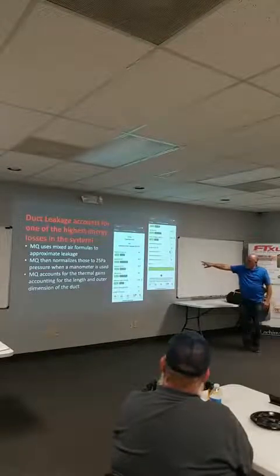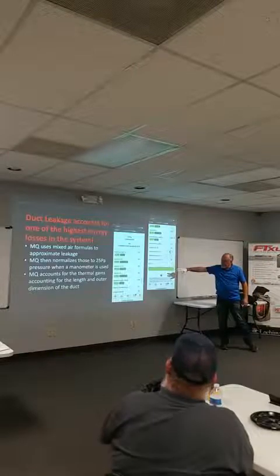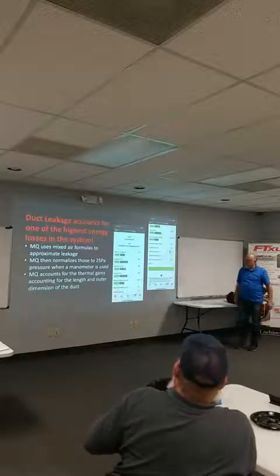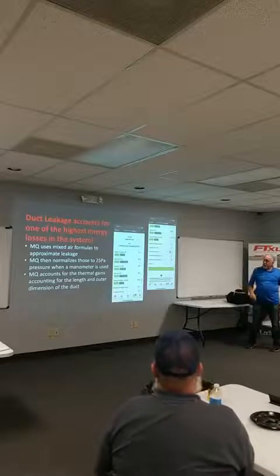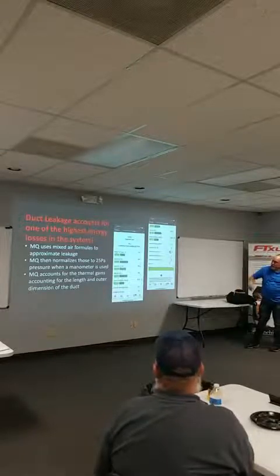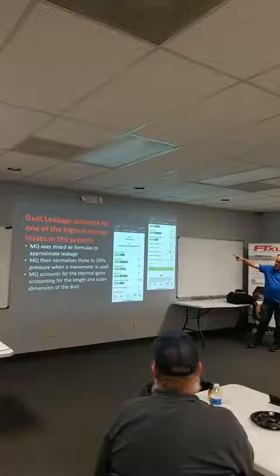So you put two mixed air probes in, one on each side, and then you measure the attic here, and it measures the static pressure. Now, going back to what you mentioned about a duct leakage test, we typically test ducts at 25 pascals. And what Measurequick does is calculate total capacity loss and then the duct leakage.